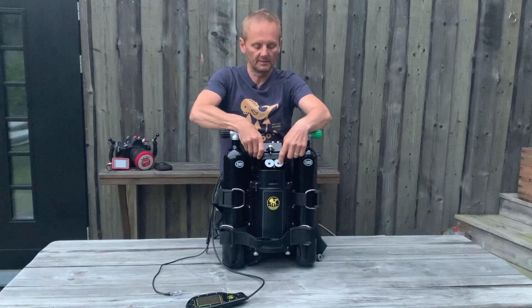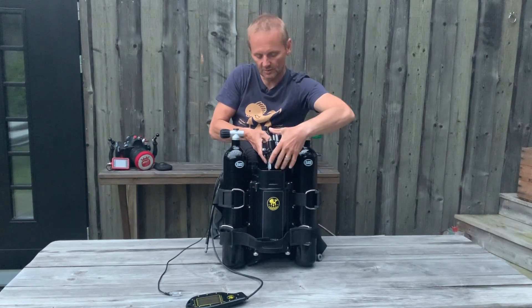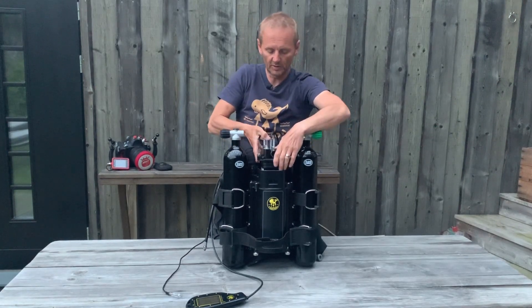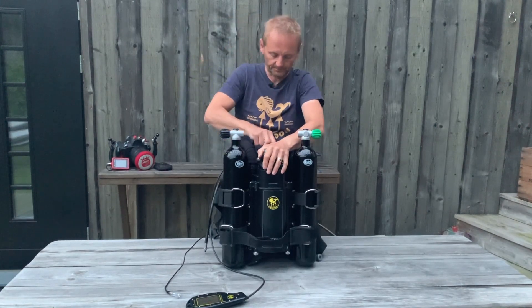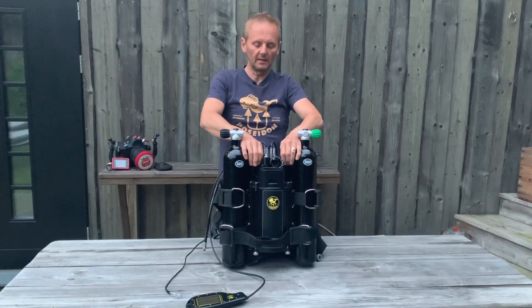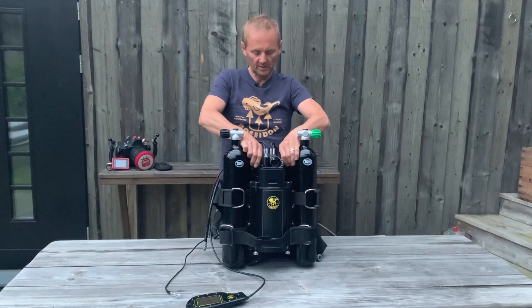This is the primary cell — the one that is most backwards or farthest away from you. This is the primary cell and this is the secondary cell. That is good to know when you are doing the calibration or trying to find out if something is wrong with the machine. We push the e-module in and we tighten the screws — only finger tight. No tools should be used here.